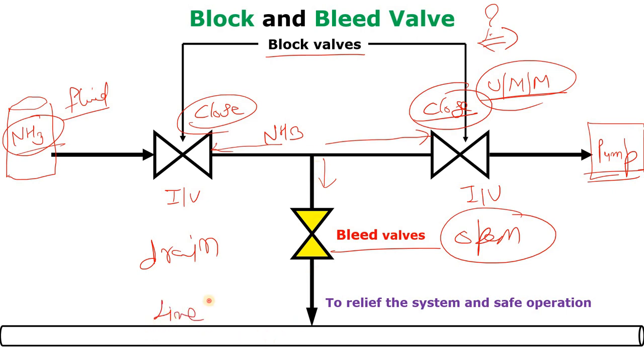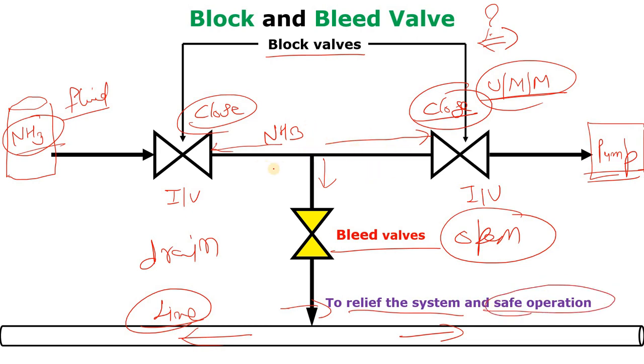This is the closed drain line, and from this line it will go to a closed drain tank. We do this to relieve the system and for safe operation. When we release all the explosive and toxic gas from this line, then only we can give our system for maintenance and other work. That is why this block and bleed valve is given in the pipeline — to relieve the system from toxic gases and for safe operation.